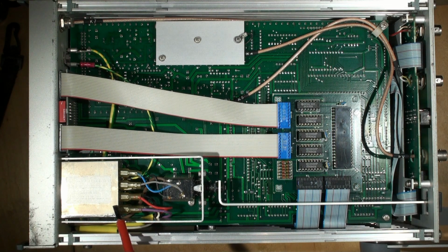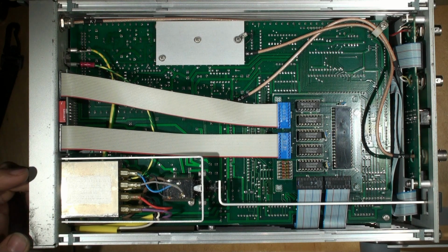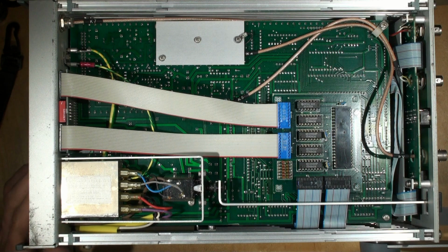I have had these things. This is a combined input filter, IEC input, mains and voltage adjustment, and I have seen these on some bits of test equipment where the internal capacitors inside have blown up and gone short. So before you start poking around disassembly, make sure there isn't a short inside the mains input socket filter, because I've seen them blown up quite often, especially on Wayne Kerr equipment and Schlumberger Solartron as well. Used one in the 70s, particularly on their multimeter range, and they often go short circuit as well inside the actual mains connector, so you have to take the whole mains IEC input fuse holder connector filter block out and chuck that away. So before you start poking around, check that first, but in this case it's not that, it's something else.